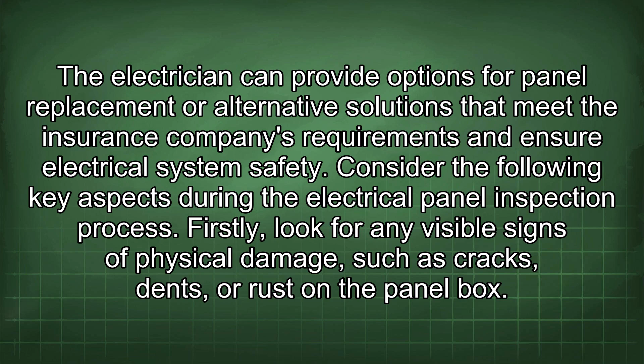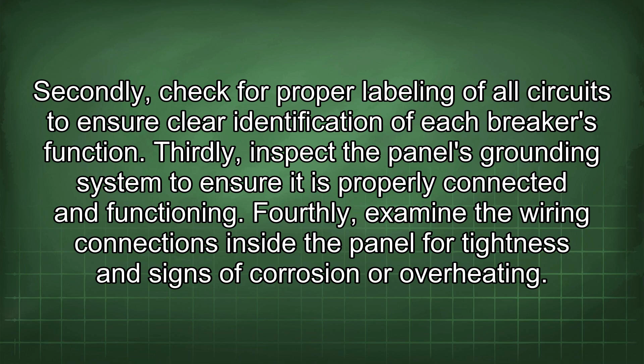Firstly, look for any visible signs of physical damage, such as cracks, dents, or rust on the panel box. Secondly, check for proper labeling of all circuits to ensure clear identification of each breaker's function. Thirdly, inspect the panel's grounding system to ensure it is properly connected and functioning. Fourthly, examine the wiring connections inside the panel for tightness and signs of corrosion or overheating.